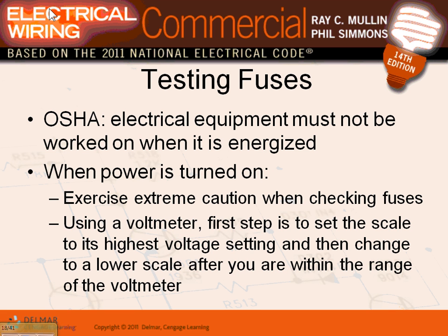OSHA says equipment must not be worked on energized. This is a few things, guys, for an electrician. You don't want to work on things energized. Power must be turned off. Voltmeter, first test. The rule when you work on equipment like this, I know you're not an electrician, guys, is first you disconnect the equipment, then you lock it and tag it. That's not enough yet. Then you have to verify that the equipment is de-energized. So you have to go measure.